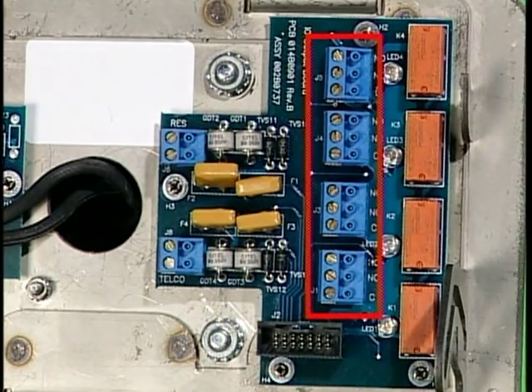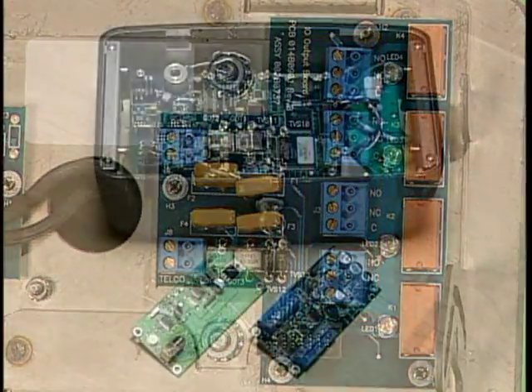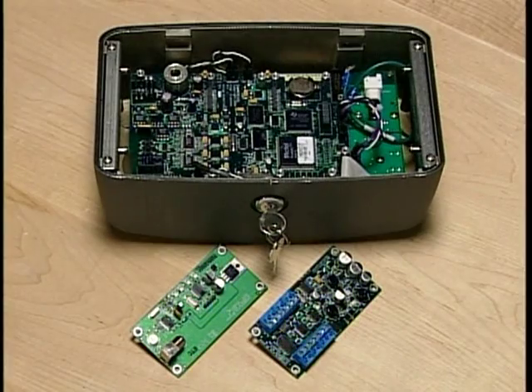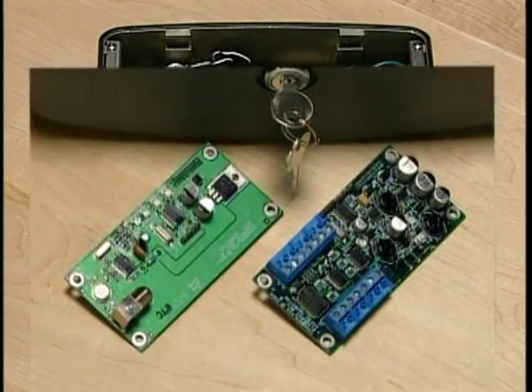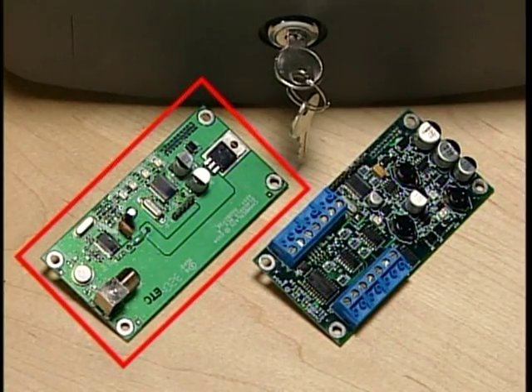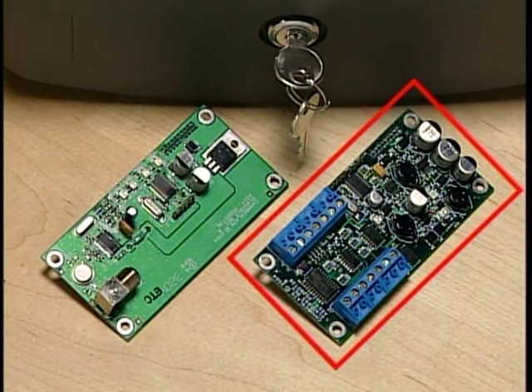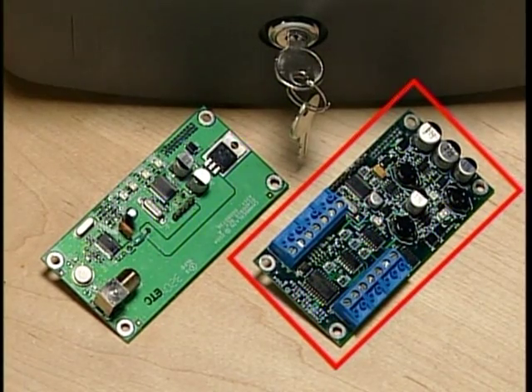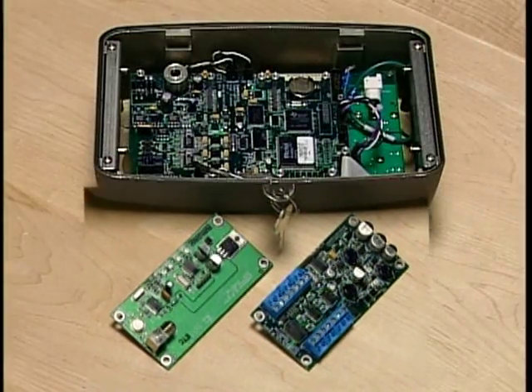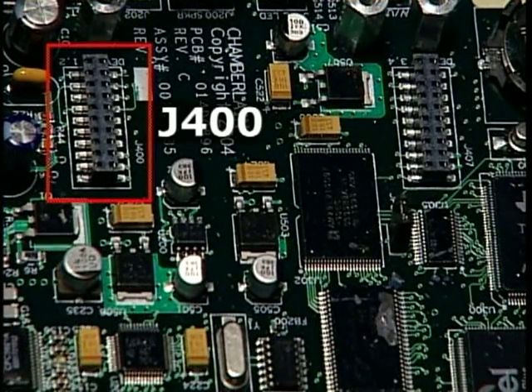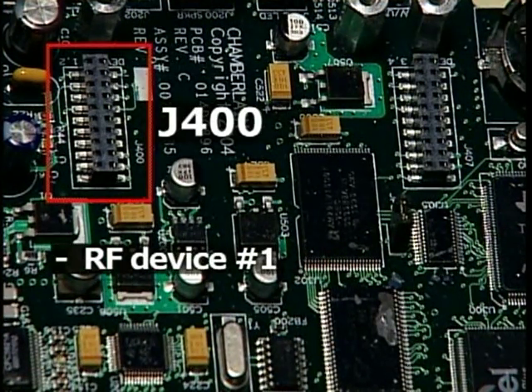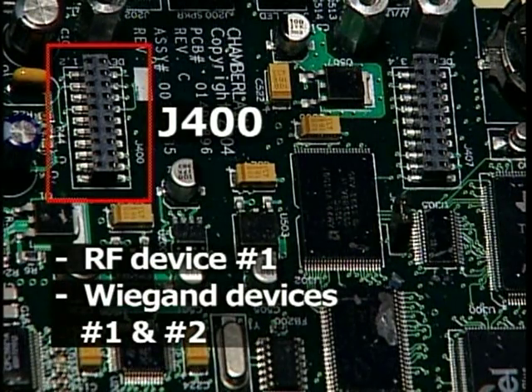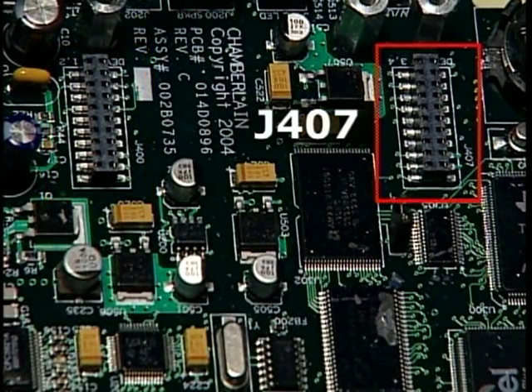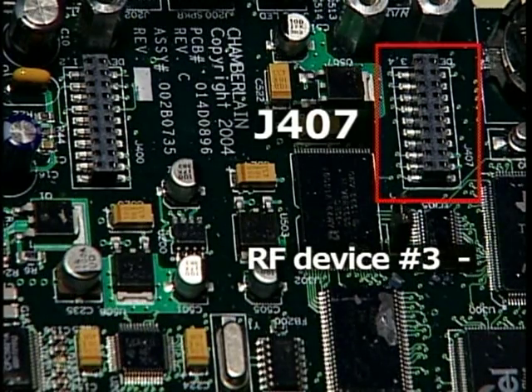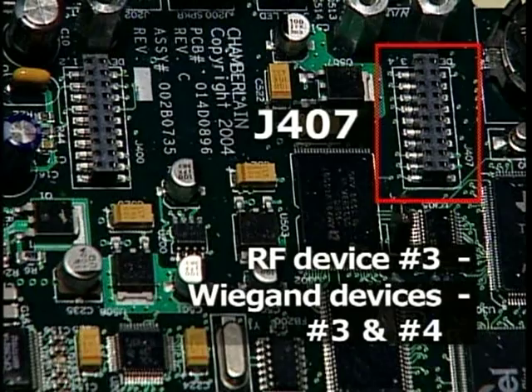The EL25 has 2 plug-in ports for the addition of optional modules. There are 2 optional modules, one an RF module for the use of passport radio transmitters, and the other a Wiegand module that can accept up to 2 26 or 30-bit Wiegand card readers or keypads. The first port is labeled J400, which is for an RF device 1 or Wiegand devices 1 and 2. The second port is labeled J407, which is for RF device 3 or Wiegand devices 3 and 4. Once the module board has been inserted into the proper port, it needs to be secured with the 4 screws provided with the module.